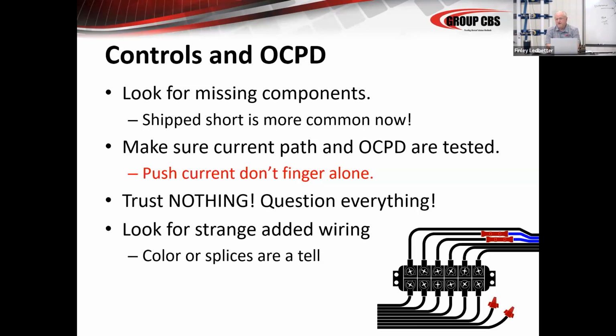Don't trust anything, question everything, is something Ernie Showalter taught me. And if you don't question everything, you'll see problems. You see here at the bottom in this little contact block, there's obviously 2 blue wires and there's a splice. That's the sort of stuff you need to be looking for. Everything should be continuous circuits, gray switchboard wire, typically SIS wire. Make sure all the radius bends and all the terminations look right.